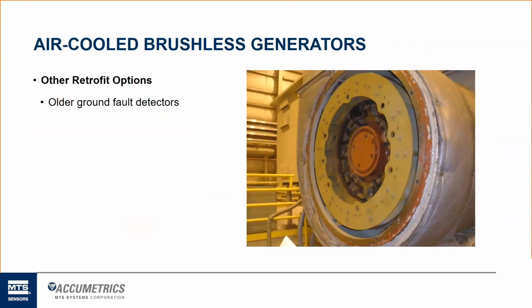Here's an example of what the exciter may look like, again, for that end of shaft system on the smaller air cooled units. This is the other retrofit option that we have that's a little more detailed than the first pictures I showed. These are the diode rectifier wheels. You can see in here where these heat sinks are. Underneath there are two parallel diodes. They run in parallel for redundancy. If one dies, the other one can still do that rectification. There's going to be a positive wheel and a negative wheel behind it. And this red piece is what's called the rotor end cap. This is all what would normally be on a smaller air-cooled unit, and is very typical of what we would see.